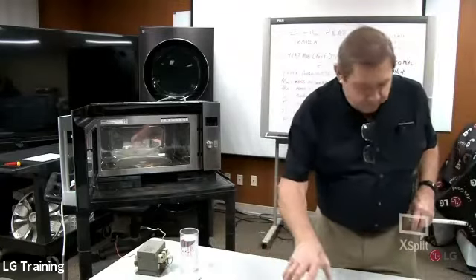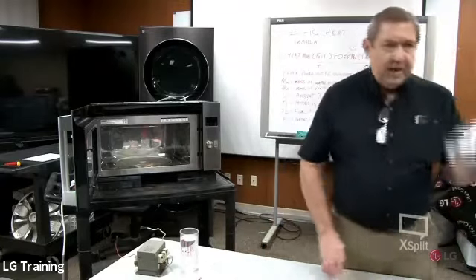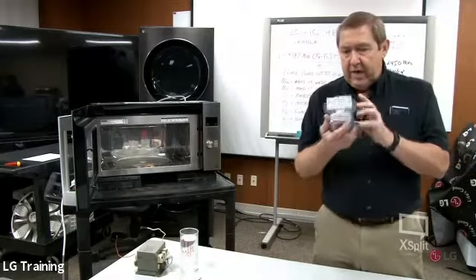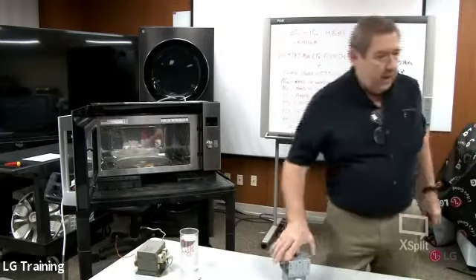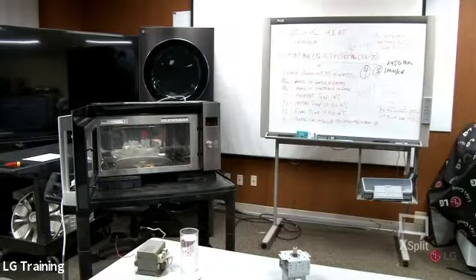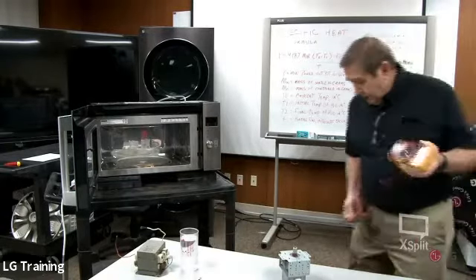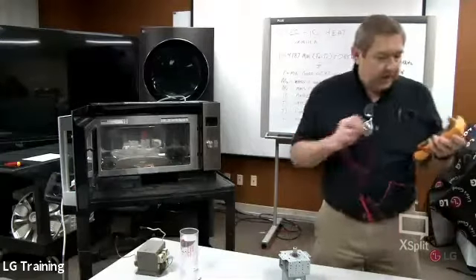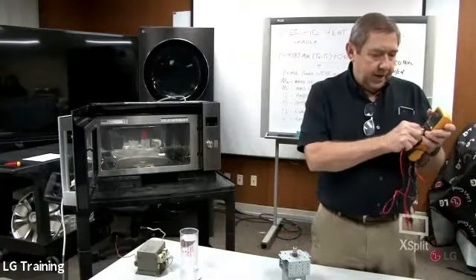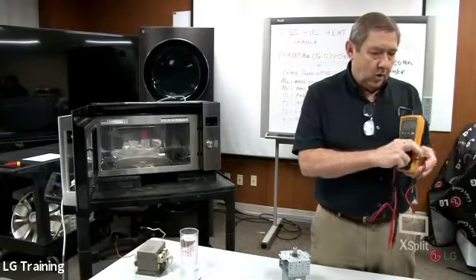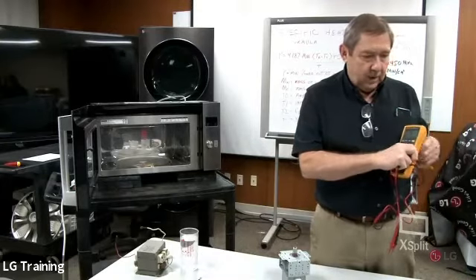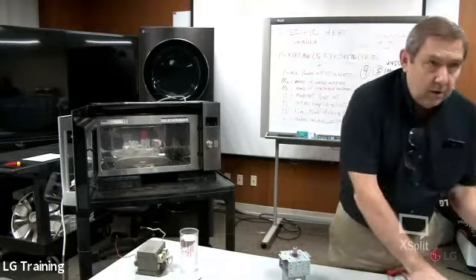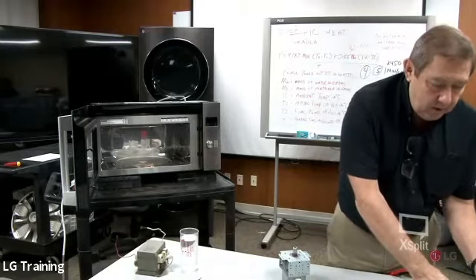But I do have a magnetron that's bad — I dug it out of the dumpster. It came back from one of our technicians, and I was looking for a magnetron and struck gold, because this one is actually bad. So typically, what I said is you're going to get less than 1 ohm when you check that. I've got this meter set for ohms — let's see if we can get this meter in there.